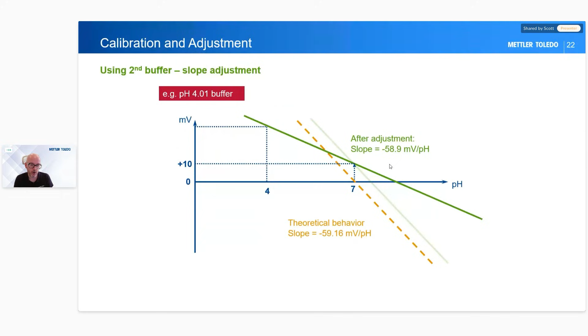The next bit for calibration is about linear and segmented. When we're doing a 2-point calibration, we can only draw one line of best fit between the 2 points. When we've got a 3-point calibration, we can do something called segmented. So instead of drawing a line of best fit, we can draw one line between points 4 and 7 in this case, and another line between 7 and 9. And if we're taking a measurement at, say, pH 8, it would take this line. And if we're taking a pH measurement at 5, it would use this line instead.